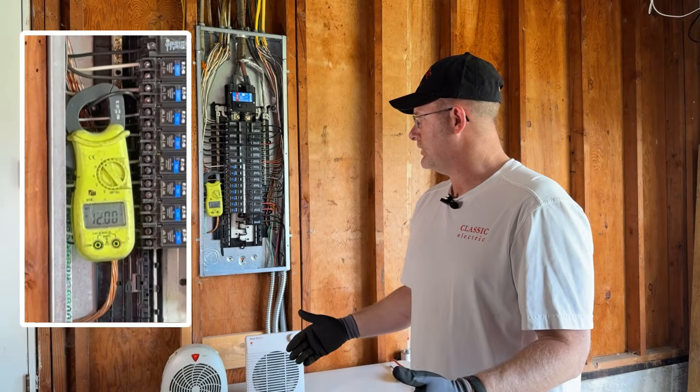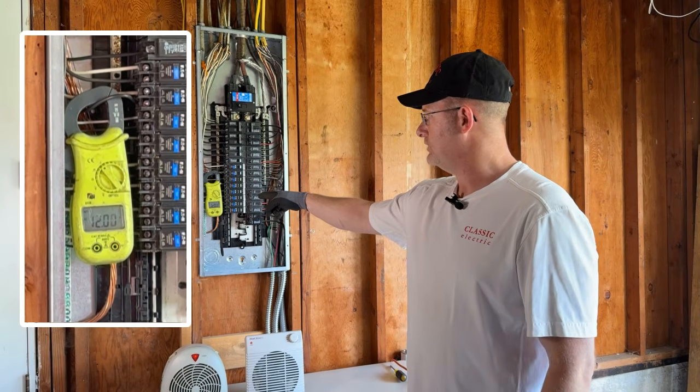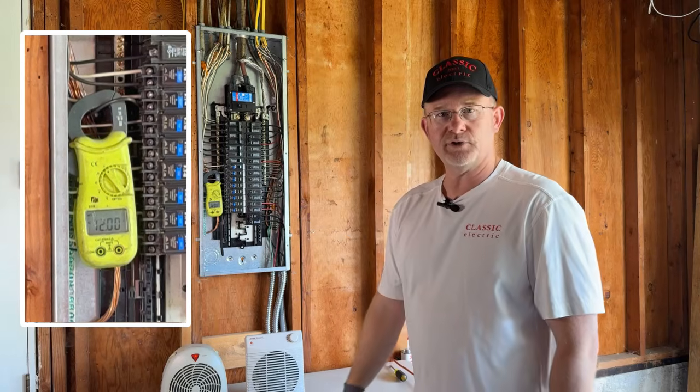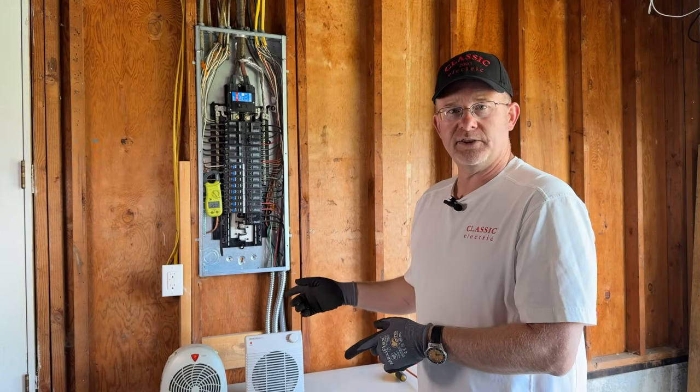Now, right now, you've got to be thinking to yourself, I'm using 12 amps, and I've got it connected to a 20 amp circuit breaker in this particular application. A lot of people are calling me and they've got it plugged into their living room or their family room and it's on a 15 amp breaker down here. Well, you're pretty much there now.